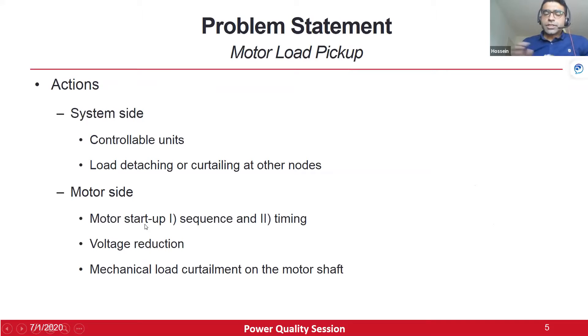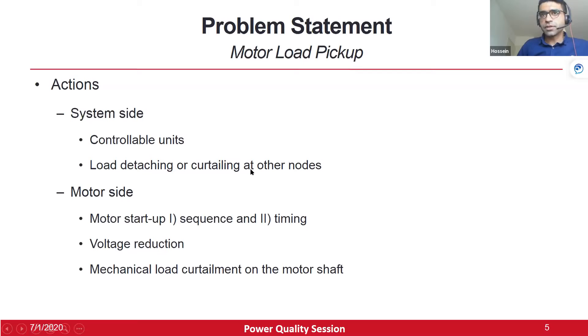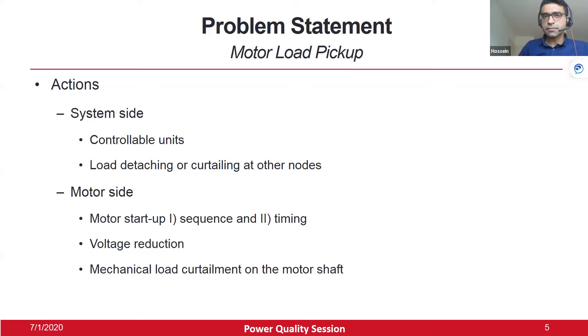On the system side, available actions include controlling dispatchable units such as DGs, detaching or curtailing loads at specific nodes in the network. On the motor side, we can change the startup sequence or timing of different induction motors, reduce the voltage at the motor hosting node using an autotransformer, or curtail the mechanical load on the shaft when starting the motor.